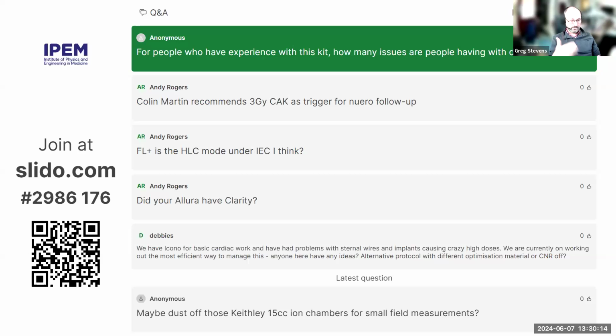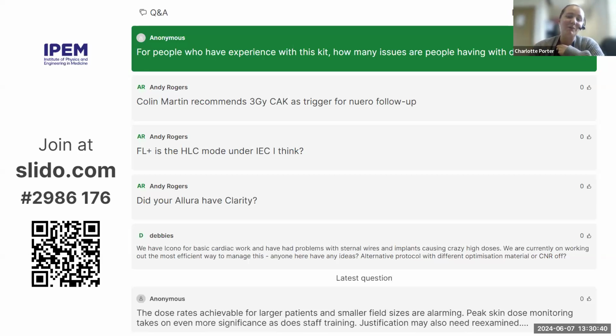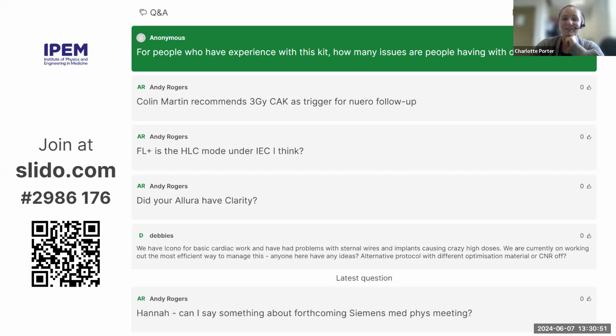I think the same iteration is going to happen here with Siemens, and I think that's just because of the commercial world that companies exist in. I don't think that's a reflection specifically on Siemens itself, or on Philips for that matter. They're both pretty good companies. Just to quickly add, with regards to the air handling unit, we've not had issues with the system since it went in, but the whole project was significantly delayed by having to resort out the air handling units before it went live. So that is definitely something to make sure that your estates and facilities teams are fully up to date on and can sort out, I guess.